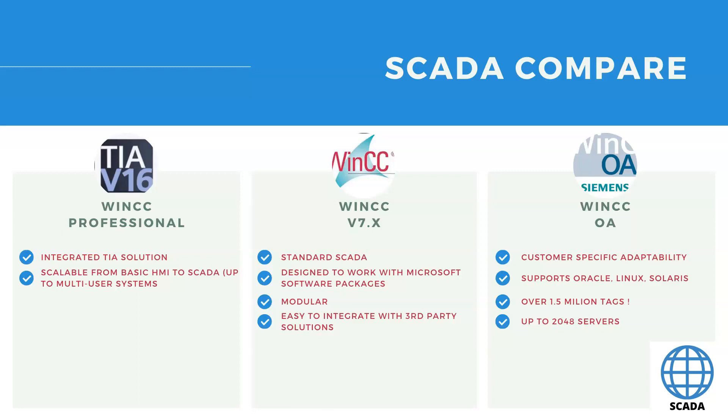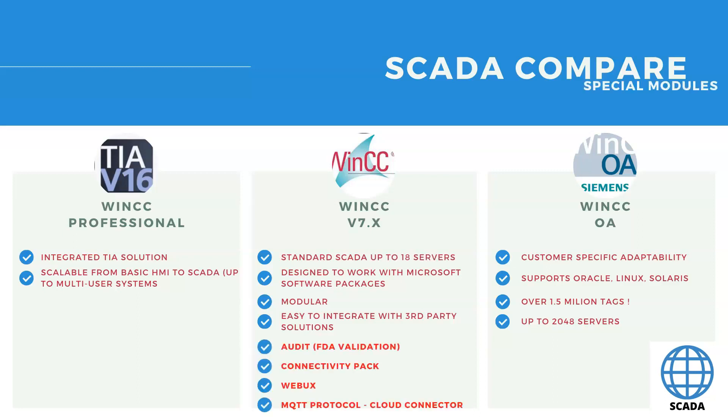WinCC OA is the biggest and most powerful system from Siemens. It has customer-specific adaptability and can work with Oracle, Linux, and Solaris — a different kind of solution. This system can work with over 1.5 million tags, which is a huge number — the biggest system I personally built had 40,000 tags. WinCC OA can work with up to 2,048 servers, so if you need a large system for a whole country — for example for gas or water infrastructure — you need WinCC OA.